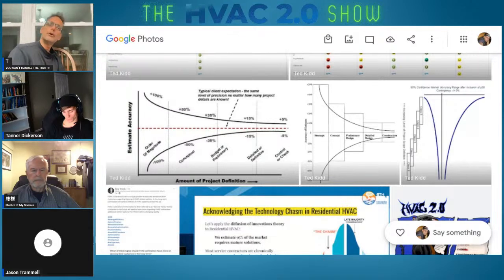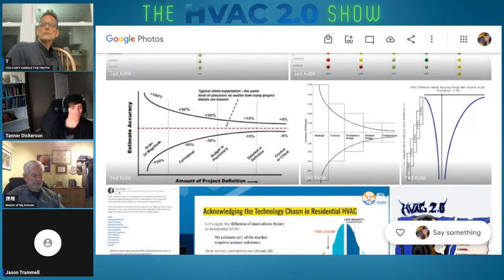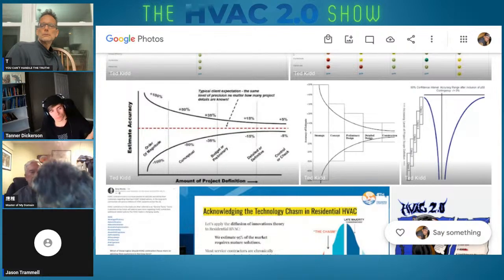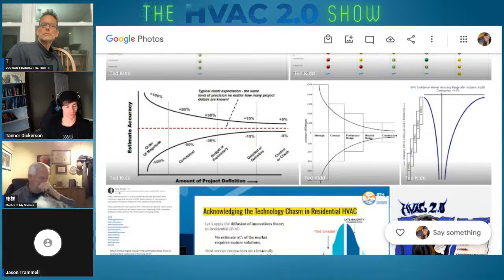Going back to the manual J thing, I'm actually going to look at the attic and the windows and do as accurate a load calculation as I can without a blower door number, to get as close as I can. It's still science. If you look at a load calc, the walls, the ceiling - I'm in a cooling dominant climate, so heat's not that big a deal to me. So ceiling load, windows, outside walls, the floor a little bit but not really, and then infiltration and ductwork leakage outside the thermal envelope are really the only factors that are going to swing it much. So I'll do as accurate a load calc as I can, because it doesn't take that much time for me to do that.